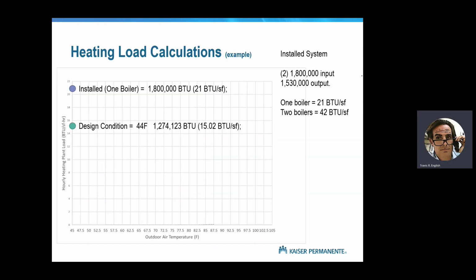Okay, so how does this actually go down? Let's look at an example. In this building, our design engineer does a calculation. The ASHRAE heating calculation comes up at 15 BTU per square foot. That is a by the book ASHRAE heating load calc. Now, everybody's going to add a safety factor to that. So they add a safety factor to that and they install the boiler at 21 BTU per square foot. Of course, this is a fully redundant system. So we actually installed 42 BTU per square foot of heating capacity.